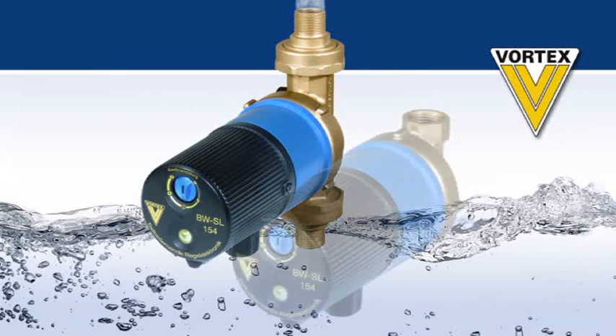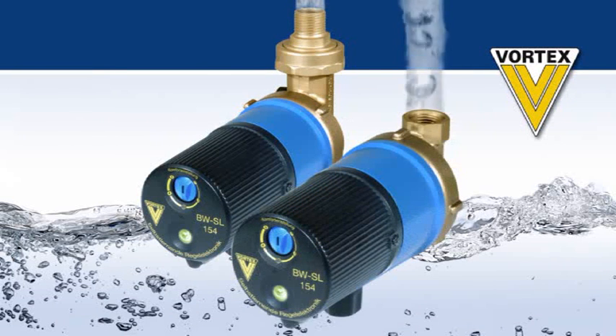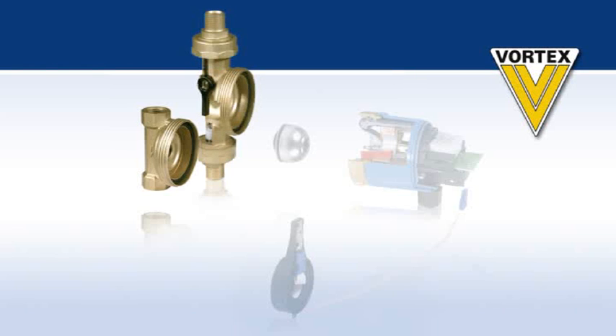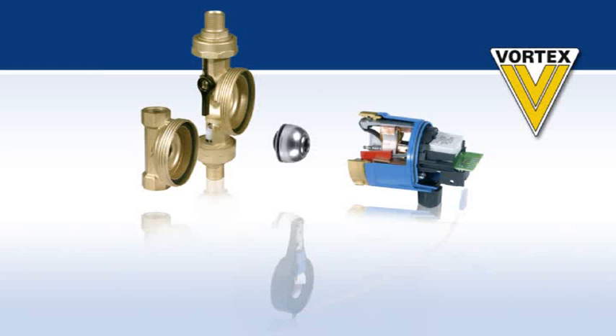The BWSL-154 is based on the principle of the Vortex spherical motor, millions of which are in service. The magnetic field generated in the motor acts directly on the magnetically attracted rotor. The special design of the rotor bearings and the bearing pin and the materials used guarantee that the spherical motor runs silently and without play. The spherical motor only needs a sealing ring between the motor and the pump housing. The motor can withstand short circuits and does not need a cutout. The rotor is easy to clean and to replace.